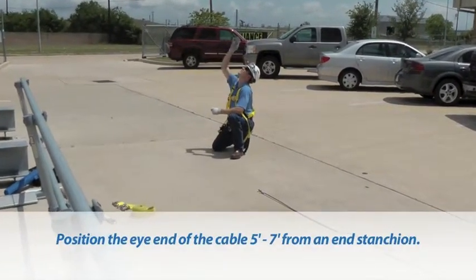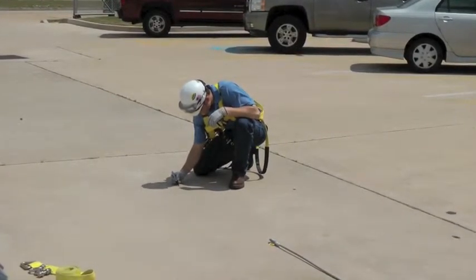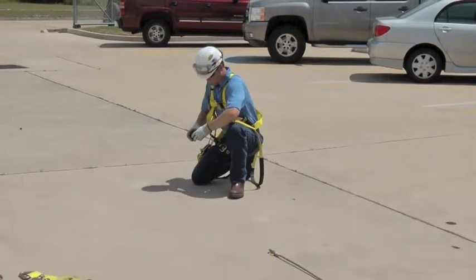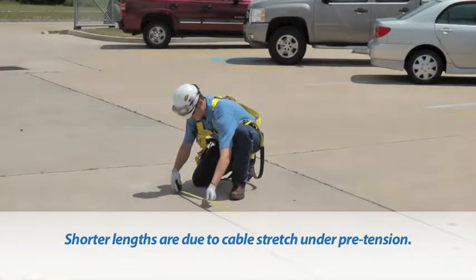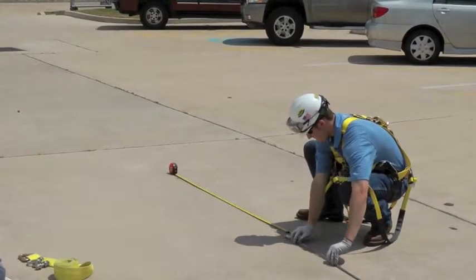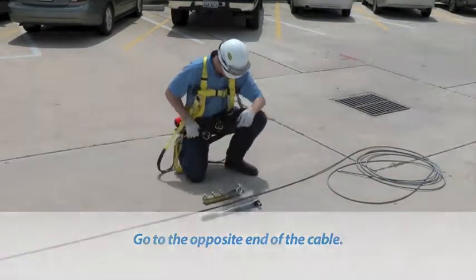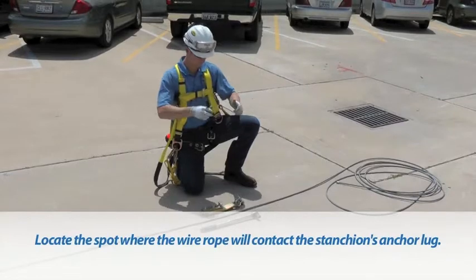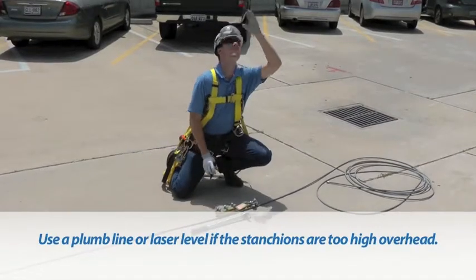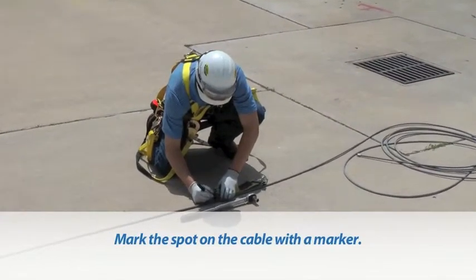Position the eye end of the wire rope so that it is about five to seven feet away from the location of one of the end stanchions. Longer spans can require up to seven feet of cable, while shorter spans are generally due to cable stretch under pretension. Proceed to the opposite end of the cable. Locate the spot on the wire rope where it would contact the anchor lug of the stanchion; a plumb line or laser level may be used to help identify this spot. Mark the spot on the cable with a permanent marker.